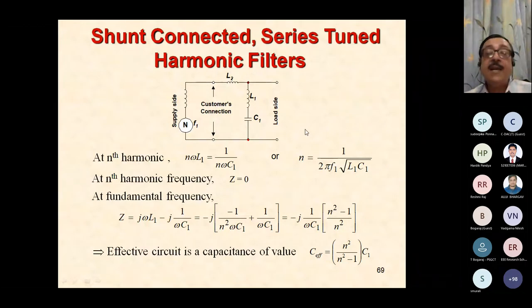This is a good solution. And plus, you have an added advantage now. This type of LC circuit at fundamental frequency behaves like a capacitance, because you will recall that any LC series tuned circuit below its resonant frequency behaves like a capacitor. And the fundamental here is below the nth harmonic resonant frequency. So it will behave like a capacitor, which means it will add to VAR compensation. It will be like you have an additional capacitor here. It will add to the VAR compensation requirement at this location. So it's good, in a double way.